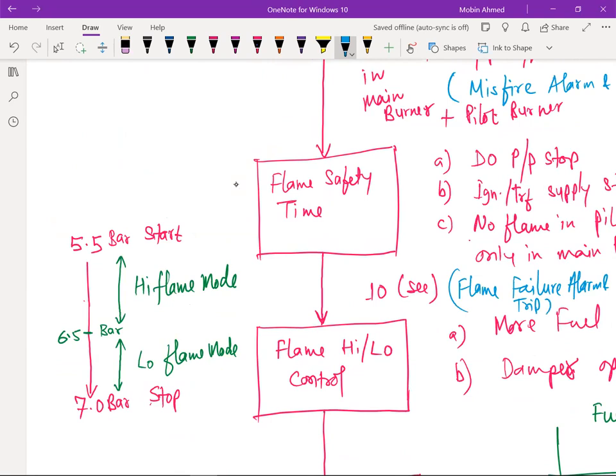Okay. Now, what could be the reason that the flame is not there? Flame failure alarm, the reasons are many. I will give you 1, 2, 3, whatever is there. So if the question is asked, you can answer that one. Okay. So for the flame failure alarm, first let's see the ignition failure. What is the ignition failure? If it is there, what are the causes of that?